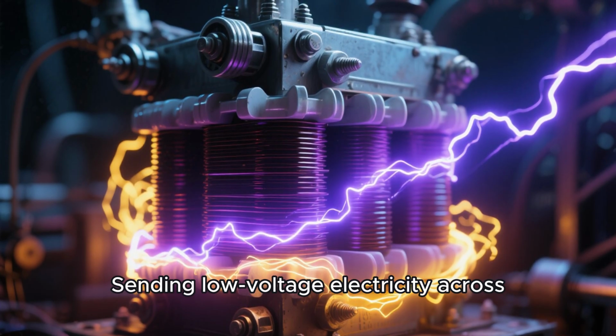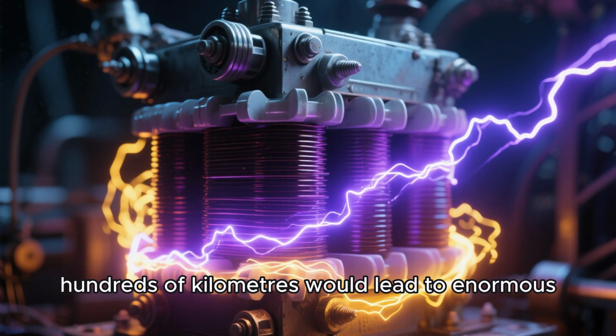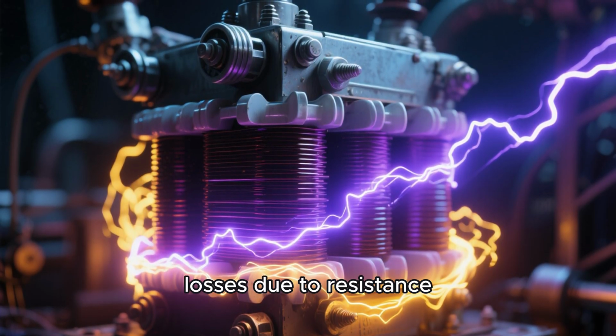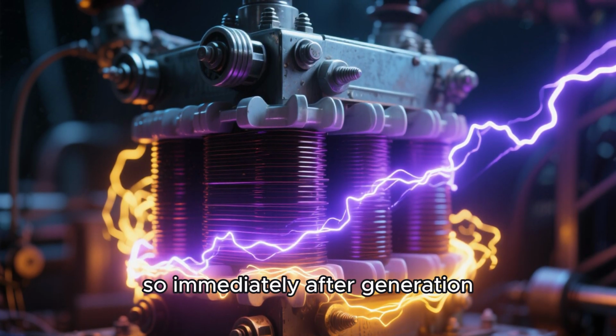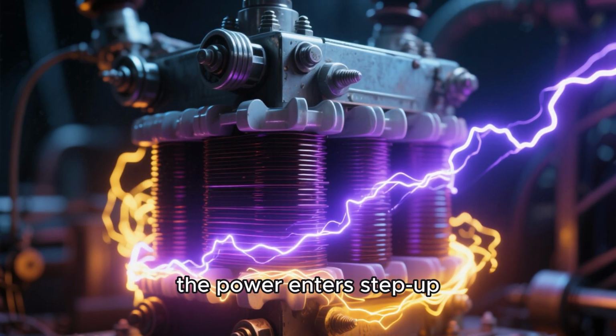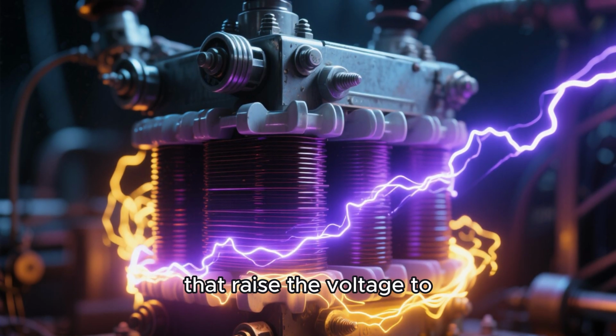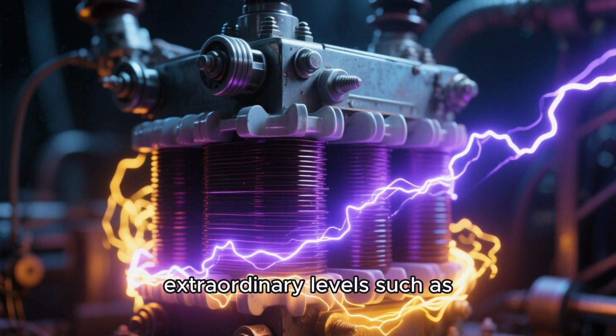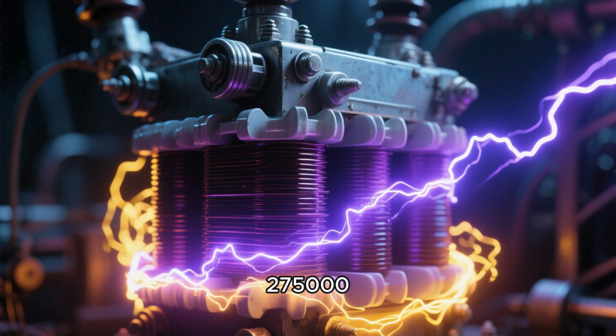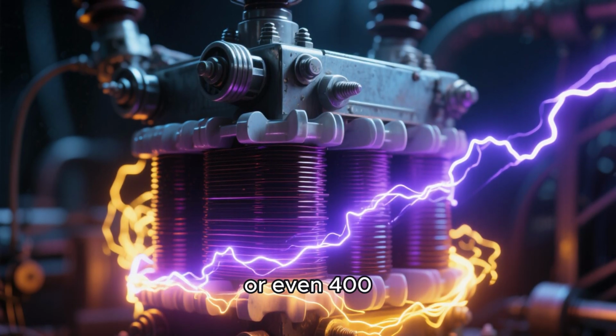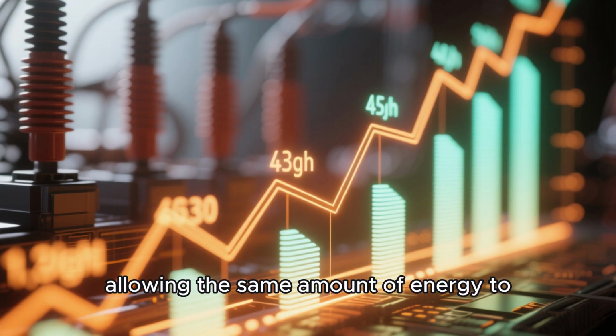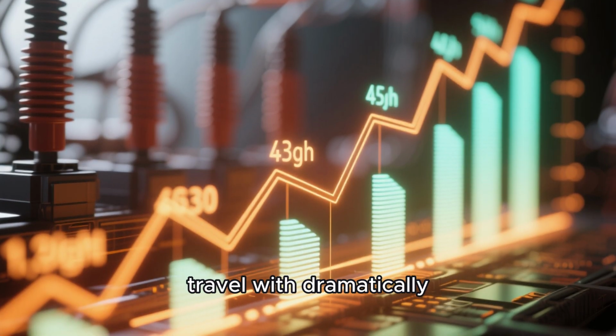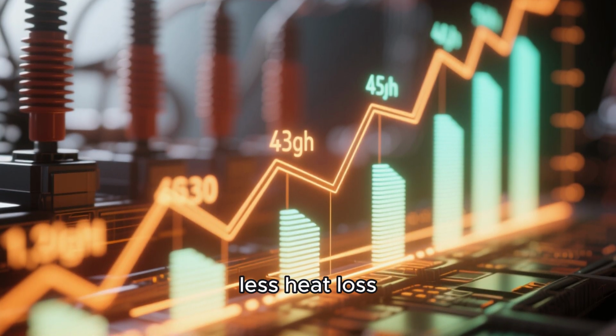Sending low-voltage electricity across hundreds of kilometers would lead to enormous losses due to resistance, so immediately after generation, the power enters step-up transformers that raise the voltage to extraordinary levels such as 220,000, 275,000 or even 400,000 volts, allowing the same amount of energy to travel with dramatically lower current and far less heat loss.